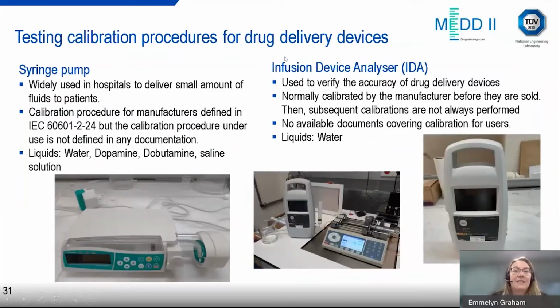If we look at the testing procedures, we've selected 4 devices, and this was in discussion with the people that helped with the questionnaire on what would be most appropriate to use. So we've selected a syringe pump. This is widely used in hospitals to deliver very small amounts of fluids to patients, and it should have a very high accuracy. There is calibration procedures which are described in this standard. These are mainly being used by manufacturers, but there isn't any calibration procedures for when it's been in use. This is not documented anywhere.